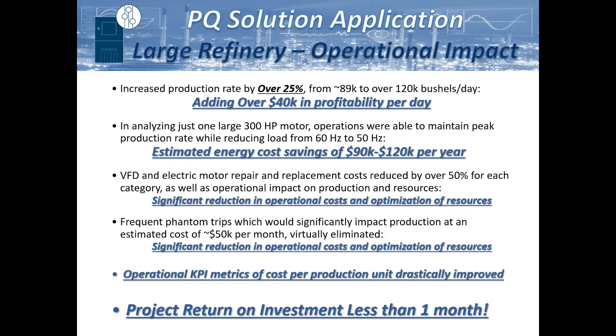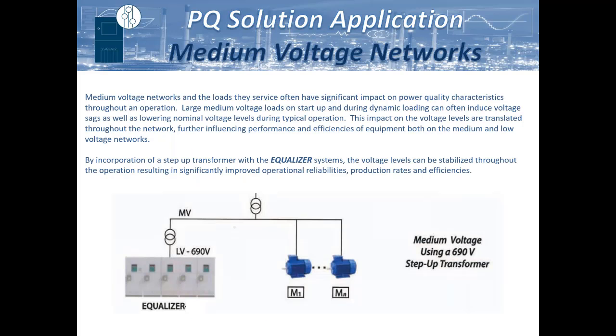But even more so, we started looking at it from a long-term basis, at their overall operational costs, their VFD repair and replacement costs, and their motor repair and replacement costs, over several years. We realized that their VFD repair and replacement costs had gone down by over 60%. Their motor repair and replacement costs had gone down over 50%. And the only marked change was the implementation and the stabilization of the network. So it can be a lot of things that aren't naturally attributed to power quality. You can also oftentimes see a very significant improvement once you provide a stable network.